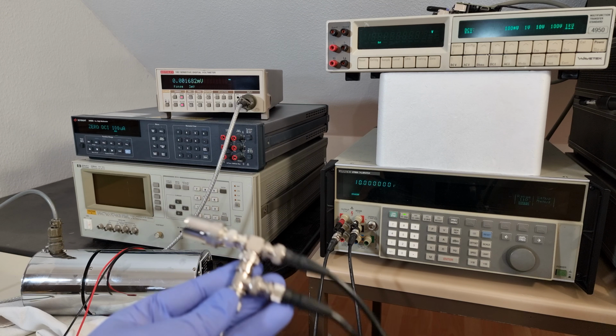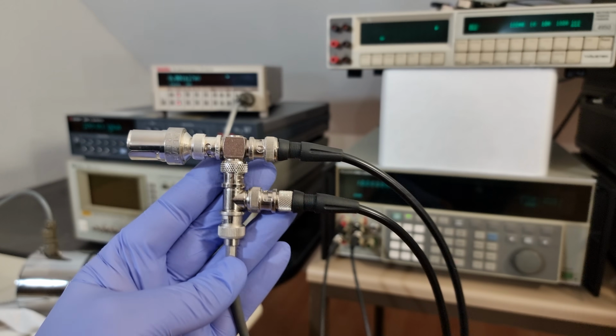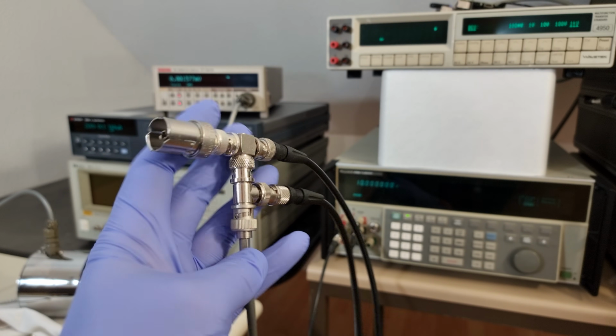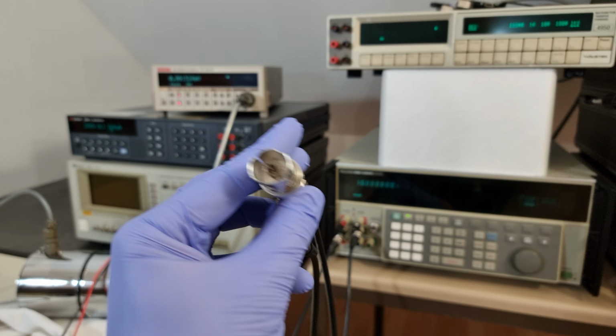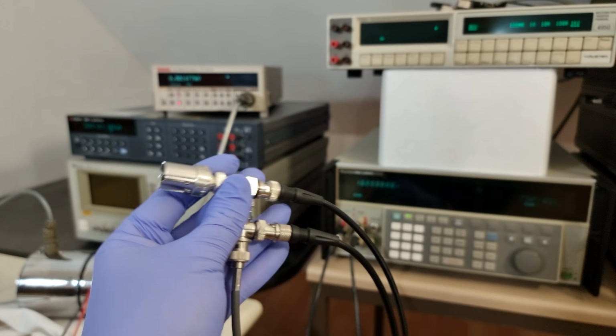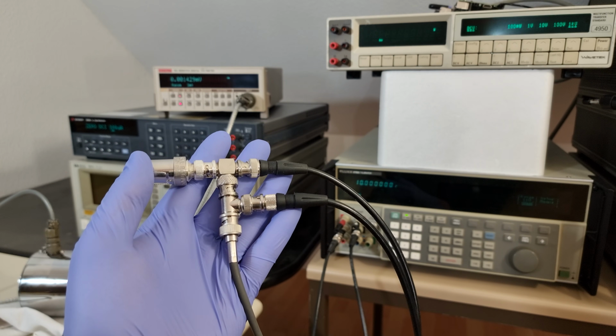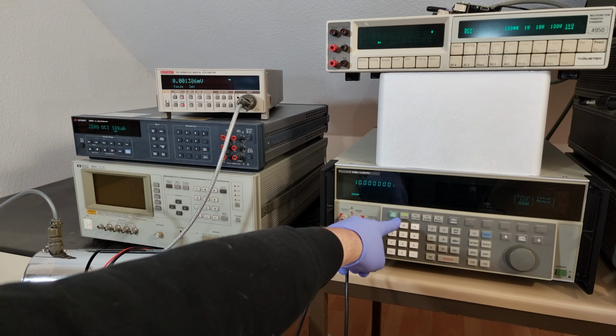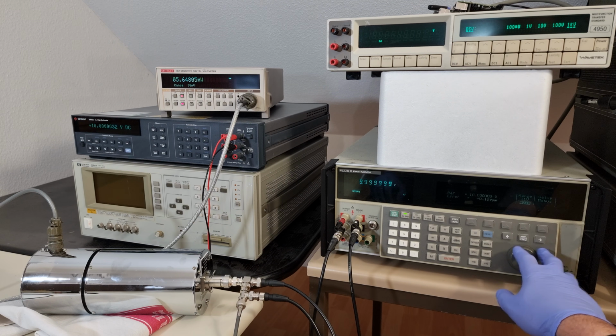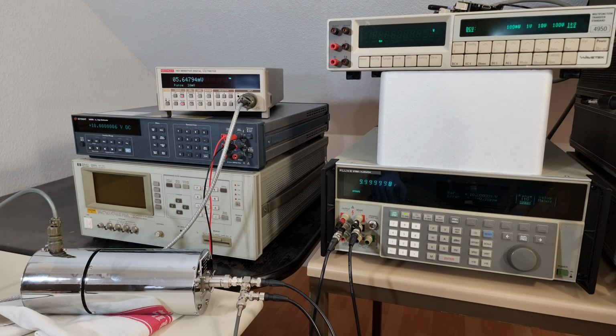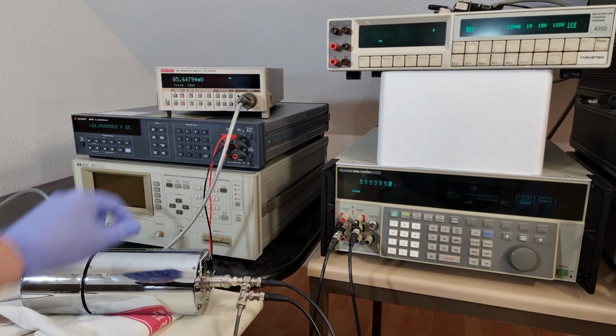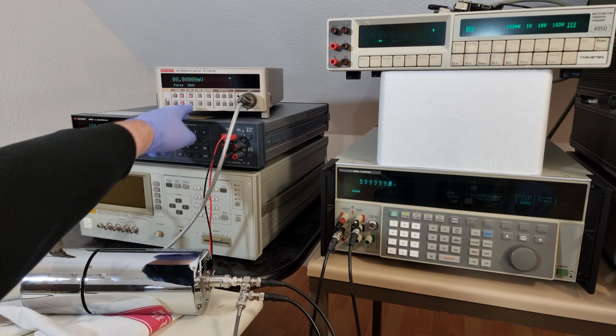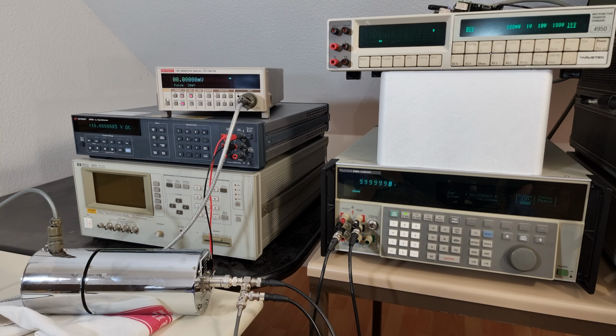One of the many disadvantages of thermal voltage converters is that they need a significant current, a couple of milliampere at least, to create the heat that is their central working principle. A current flow through a cable resistance means that there's going to be a voltage drop between the source and the destination, so I've configured the calibrator for 4-wire remote sensing. I'll use the freshly A-CALed 3458A to fine-tune the calibrator's output to as close as possible to 10 volt DC. Another TVC disadvantage is that they have a longish settling time, but after a while the thermocouple reading on the nanovolt meter stabilizes. Then we can zero it digitally, so that we get a zero reading again whenever we inject an equivalent 10 volt RMS signal into the converter.